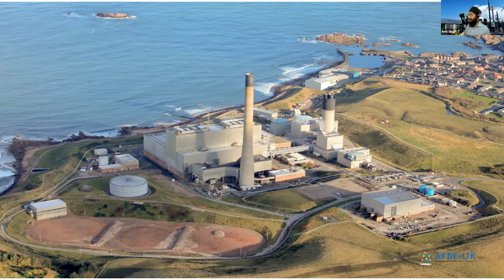The gas pipeline runs for 16 and a half kilometers, a new PRS supply was put in - the pressure reduction station - and then it feeds out to our gas turbines: gas turbine number 11, gas turbine number 12, and gas turbine number 13. From there, on the discharge side of the gas turbines, there are heat recovery steam generators - pretty much three boilers over here.